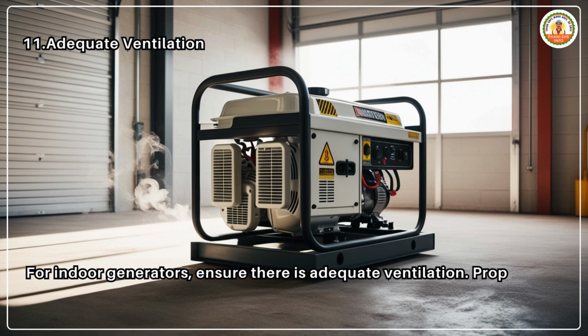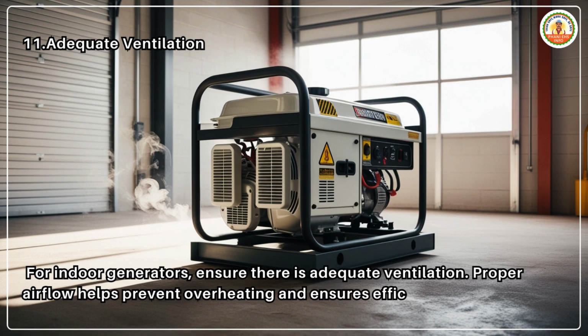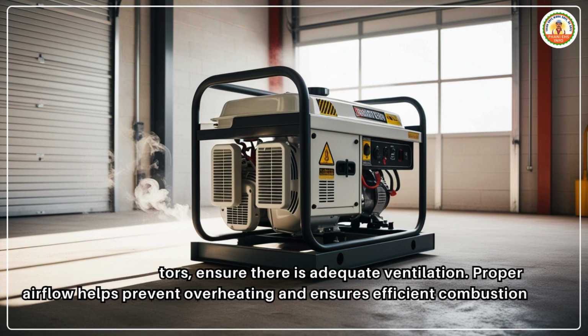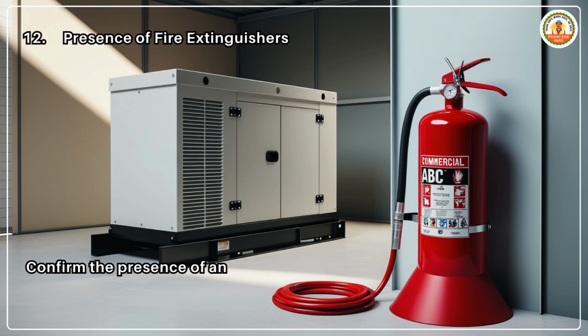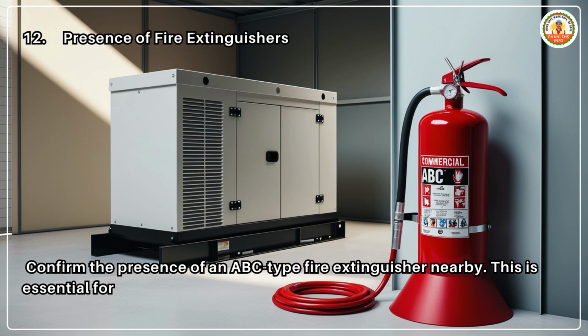11. Adequate ventilation. For indoor generators, ensure there is adequate ventilation. Proper airflow helps prevent overheating and ensures efficient combustion. 12. Presence of fire extinguishers. Confirm the presence of an ABC-type fire extinguisher nearby. This is essential for emergency response in case of a fire.